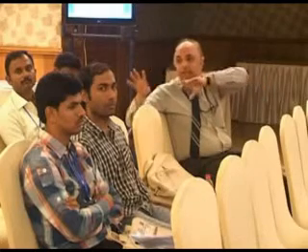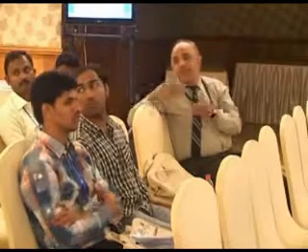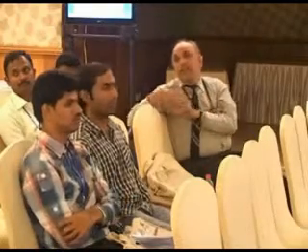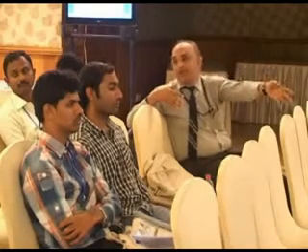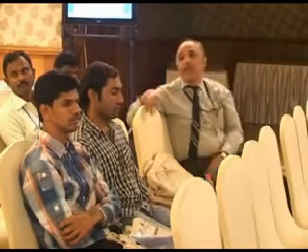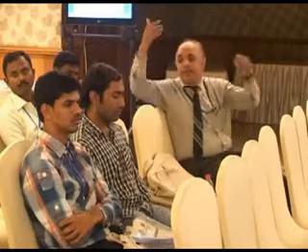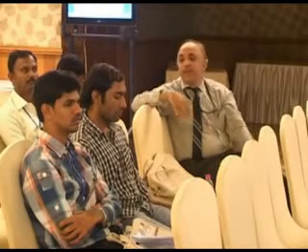So that is also one of the parameters you look at. If you want to make a study of slagging and fouling, you have to look at the ash fusion temperature and ash chemical constituents. But when you talk of carbon losses, whether you are getting so much carbon in the bottom ash and so much unburnt carbon in the fly ash, then you say that my efficiency has gone down. It's not only because of these parameters, it's also the reactivity. How much time, in milliseconds or microseconds, is the coal able to release energy and immediately become ash and go out of the boiler. So that we need to look at.